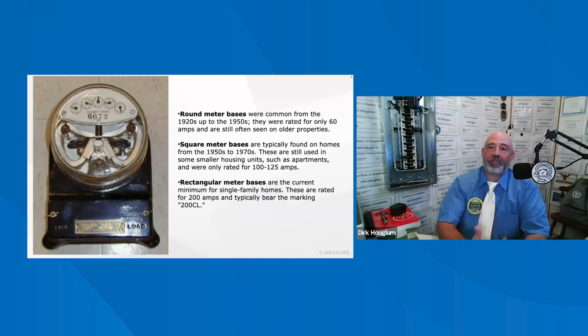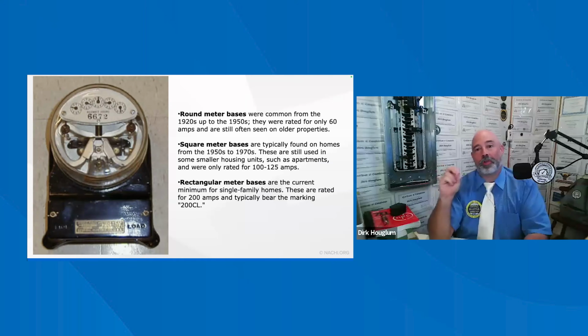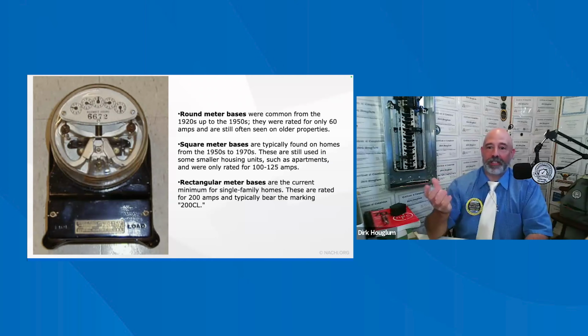Okay, here are some cool ones that I've seen too. The meter is a rated component like any other, so the ampacity of the meter and its base cannot be lower than the stated total available amperage. As meters have increased in capacity over the years, the meter bases have changed. The very earliest meters, such as the inspection image here, had a separate base and were typically rated for only about 30 amp supply. Understanding the meter base is an important part of evaluating the maximum available amperage in the home, but it should not be relied on completely when sizing a service.